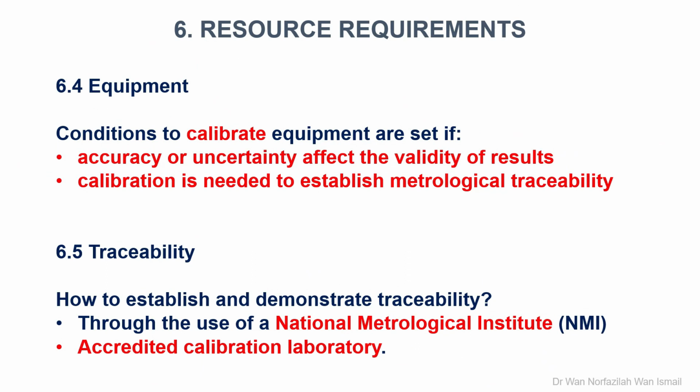Clause 6.4 Equipment. Standards, reference materials, reagents, and software are now also considered as equipment. Conditions to calibrate equipment are set if accuracy or uncertainty affect the validity of results, and if calibration is needed to establish metrological traceability.